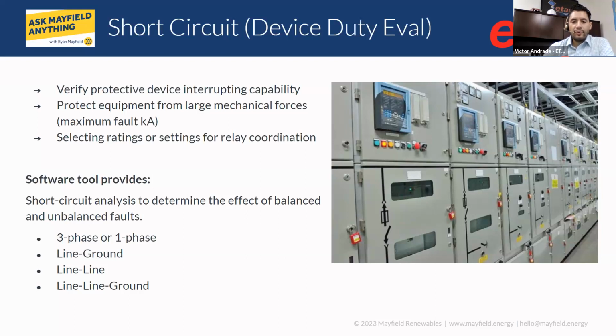So most of you are probably familiar with breaker interrupting rating or fuse interrupting rating. That's the kA rating that you see printed on the nameplate of the equipment. So whether it's a 42 kA or a 65 kA, what you're doing in a modeling environment like ETAP is, when you perform your design and you select the equipment, every piece of equipment has a library associated with it that you select from in the software.